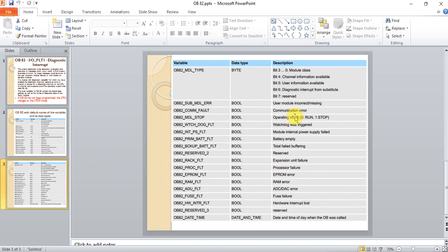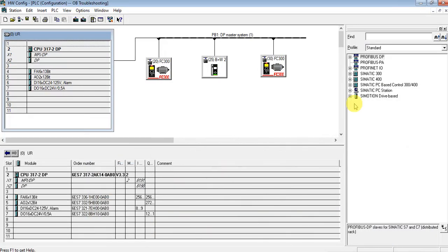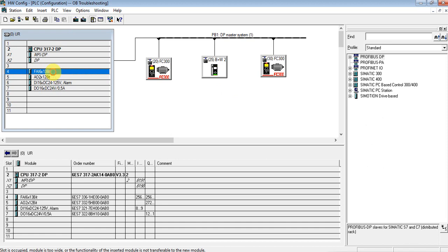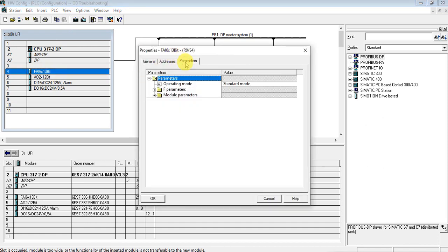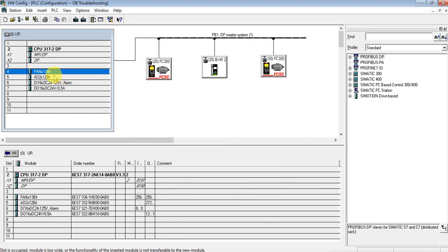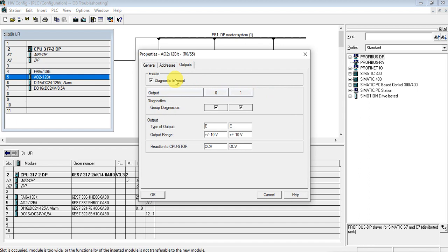Here are some of the variables. Let's first go to the hardware configuration — I have already added all my input modules here. The input/output module must have the diagnostics interrupt feature enabled. To monitor faults, we have to select the modules correctly; all my modules have this diagnostics interrupt option enabled.